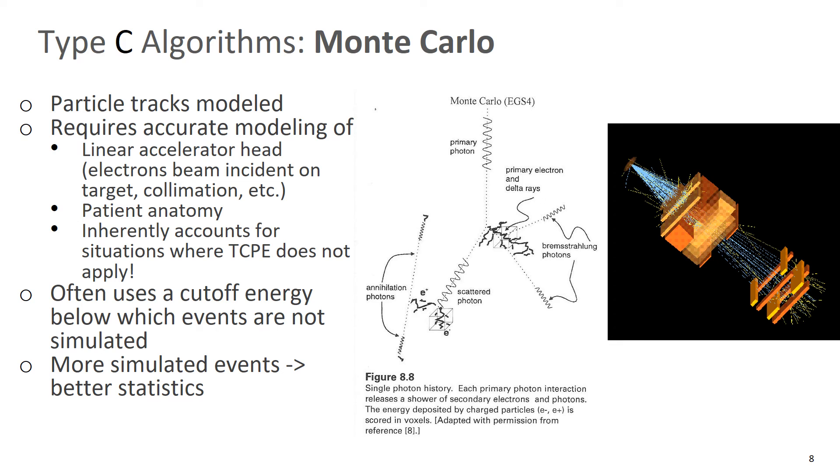It requires accurate modeling of the linear accelerator head and the patient anatomy. It inherently accounts for situations where transient charged particle equilibrium does not apply. So that's a big advantage. One reason why it's the gold standard. It often uses a cutoff energy below which events are not simulated. And more simulated events equals better statistics.